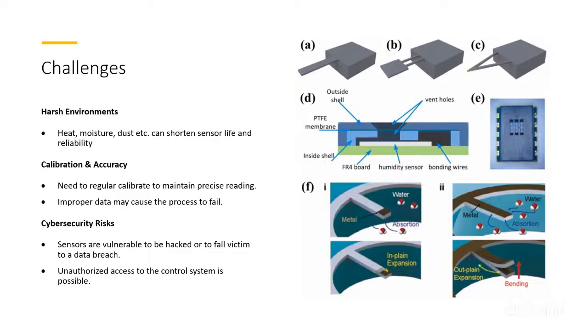Most manufacturers offer instructions on how you have to carry it out. Some are quite complex and some are less complex. So these pose challenges, and you have to try to ensure you have precise readings during calibration of these sensors, because improper data can result from poor calibration of the sensors.